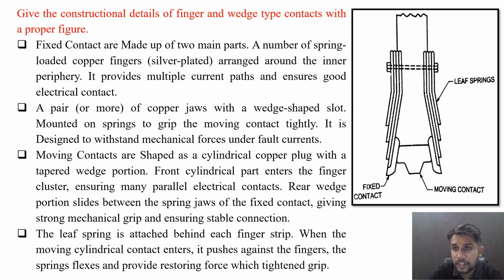So here you can visualize this. These are the leaf springs which create the pressure on the contacts. These are fixed contacts too. And this is the moving contact, a wedge type. So it is a finger and wedge type contact. Here you can visualize the multiple fingers, across which the leaf spring is provided. So this is how the finger and wedge type contacts of a circuit breaker can be constructed.